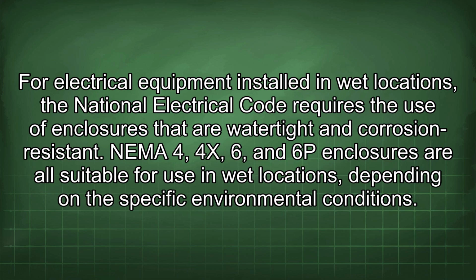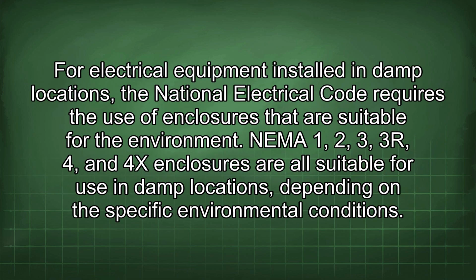For electrical equipment installed in wet locations, the National Electrical Code requires the use of enclosures that are watertight and corrosion-resistant. NEMA 4, 4X, 6, and 6P enclosures are all suitable for use in wet locations, depending on the specific environmental conditions. For electrical equipment installed in damp locations, the National Electrical Code requires the use of enclosures that are suitable for the environment. NEMA 1, 2, 3, 3R, 4, and 4X enclosures are all suitable for use in damp locations, depending on the specific environmental conditions.